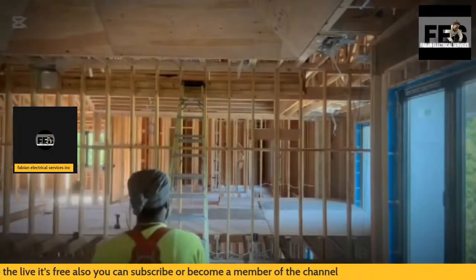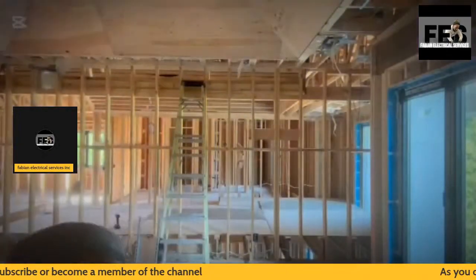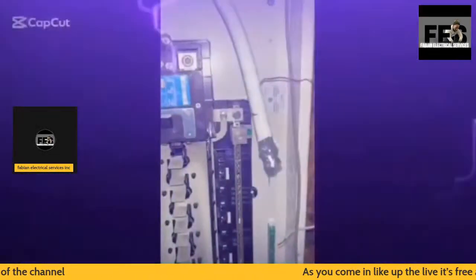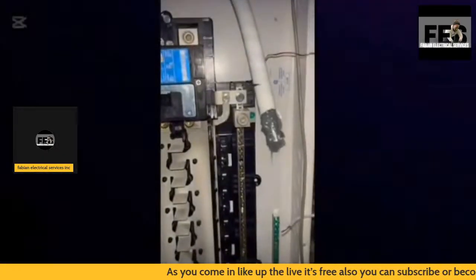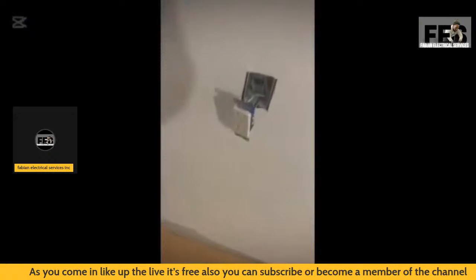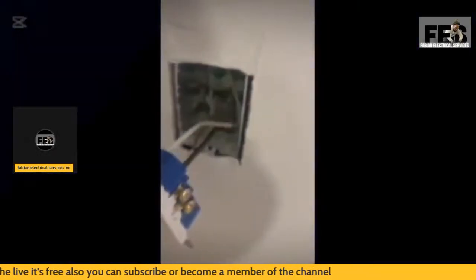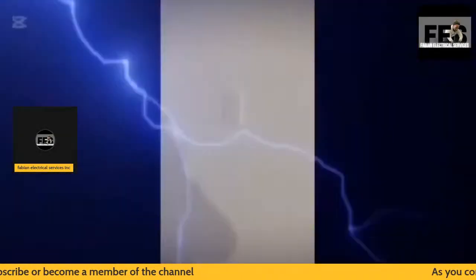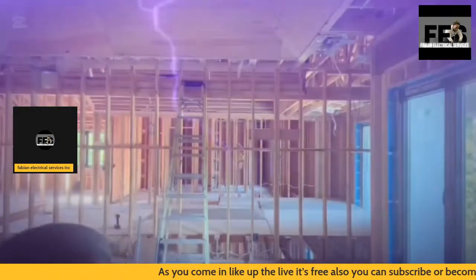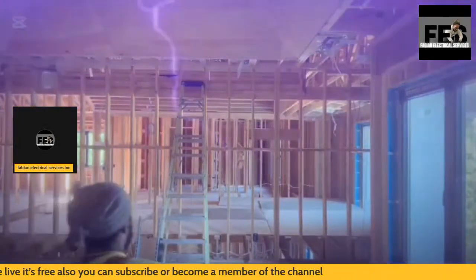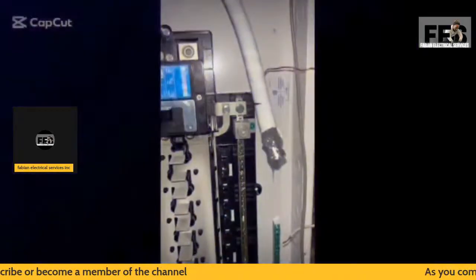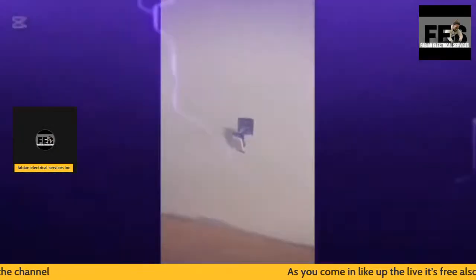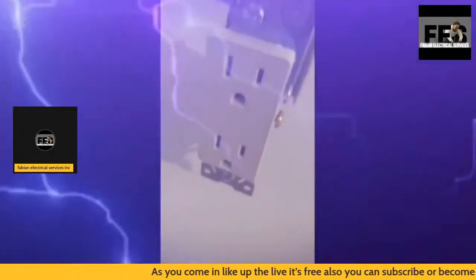You know, the ground wire provides a low resistance path for the electricity to flow back to the source, tripping the circuit breaker and preventing shock. That's what it does. A lot of times fires can occur when you don't have that grounding, and when your wire does start to overheat, it's not going to trip back at the breaker. So that's the main importance of the ground, to trip the breaker, to shut it down, to shut down the fire from happening, from spreading. Of course, no one wants to have that, right?